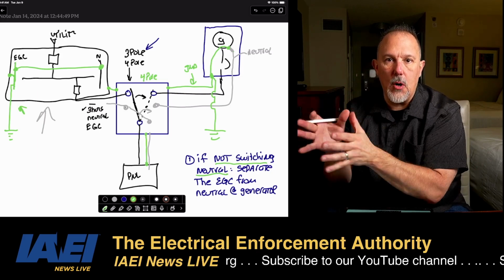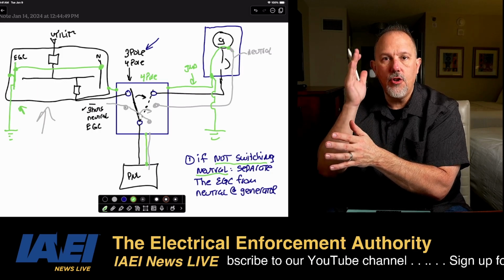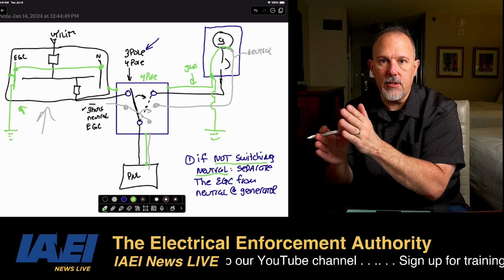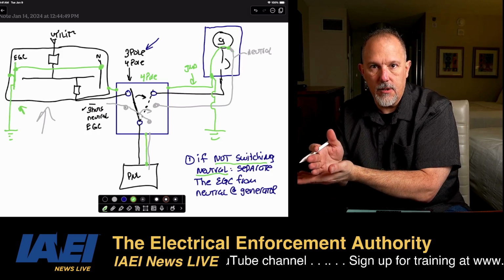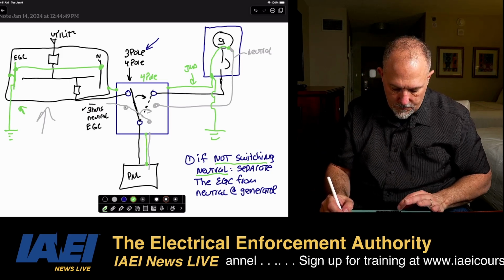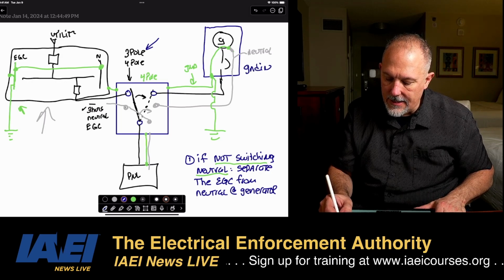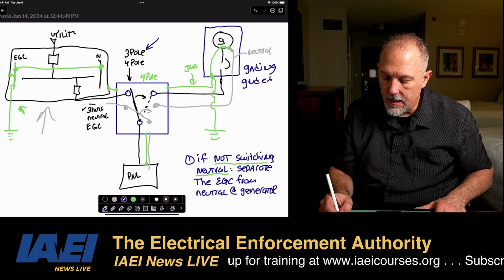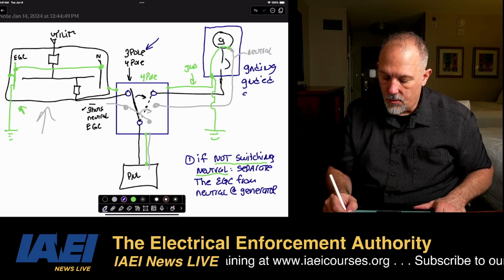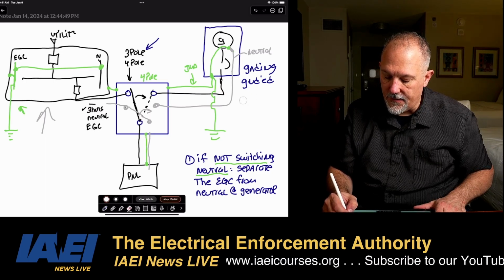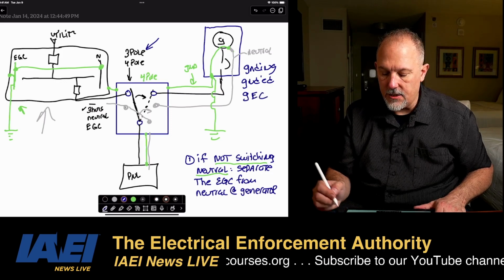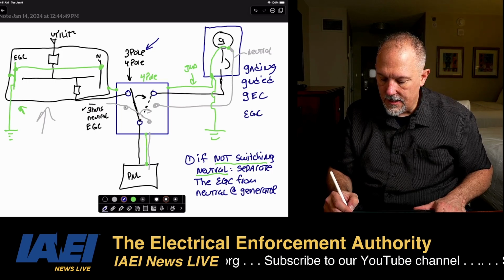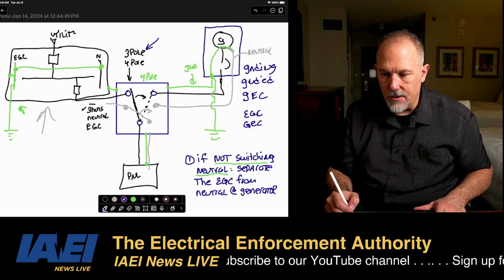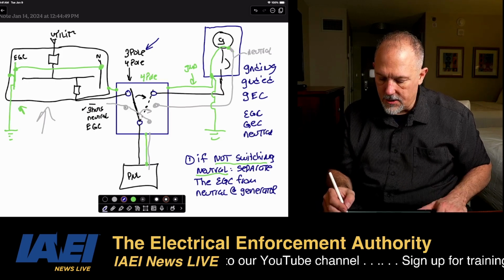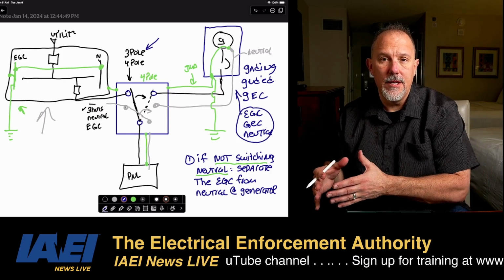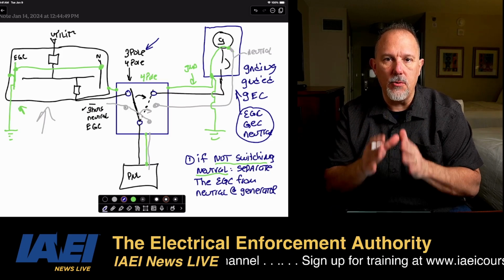And now you have to derive the bonding in the generator between your grounded conductor, your neutral, your grounding conductors, and your grounding electrode conductor. Okay, so you have your grounding conductor, your grounded conductor, and your grounding electrode conductor, right? So your EGC, your GEC, and your neutral, for lack of a better word, your grounded conductor, are all bonded in the generator. But don't do that bonding if you're only going to have a 3-pole switch.